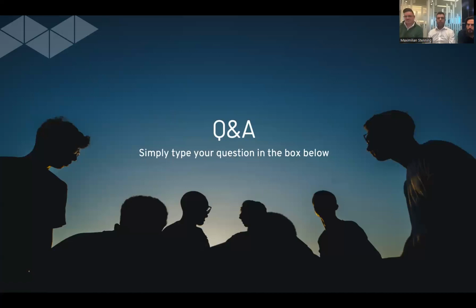I'll answer that. We use a couple of brands, and just this year, Trina Solar, who's our major brand and we're their major client in APAC, have outlasted their warranty. They turned 25 years old this year. Typically solar panels come with a 25-year warranty. Some of the newer panels that we're using come with a 30-year warranty, and they do last that long. Over about 100 megawatts of installations, we've only had about 200 or 300 kilowatts of warranty issues in the last 10 years as Smart Commercial Solar. So really they are pretty robust.